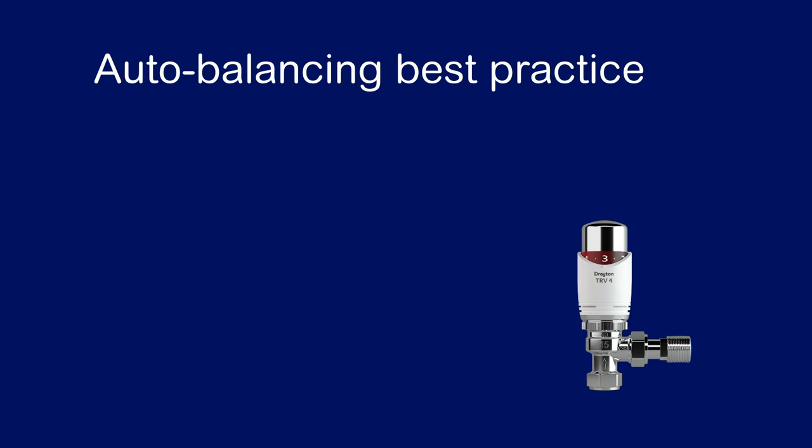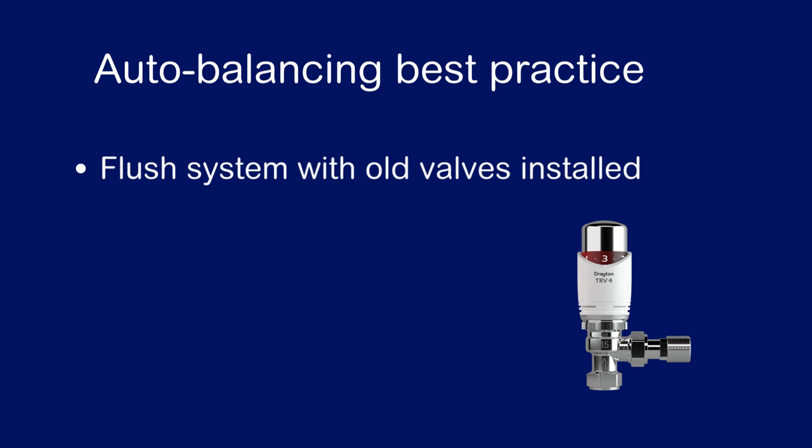Here are some best practice tips when using Drayton's auto-balancing TRVs. Firstly, you need to ensure that the system is clean and free from any debris. It is a good idea to have the system flushed with the old bodies installed and fit the Drayton auto-balancing TRVs afterwards to make sure that the small aperture within the valves is kept clean. Next, you need to make sure the flow follows the flow direction arrow on the body and orientate the head accordingly.